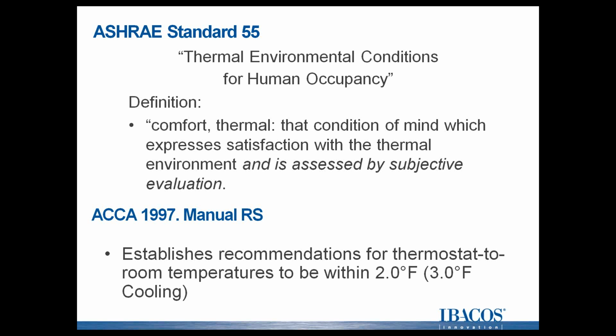Let's step back and talk about system design and some of the challenges currently being faced by low-load homes. Something very significant, that becomes more and more prevalent as the overall shell and enclosure load goes down, is the disparity between heating and cooling loads and the amount of airflow needed to satisfy that load.